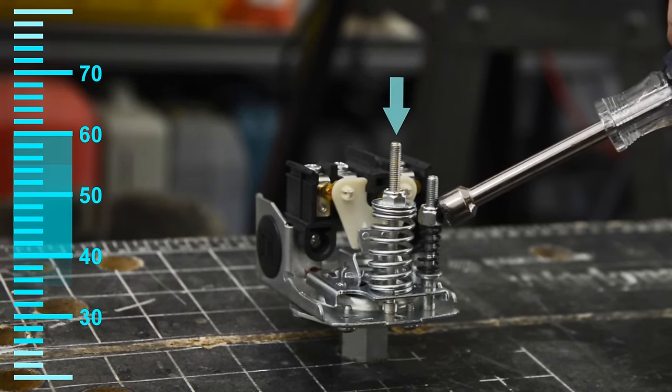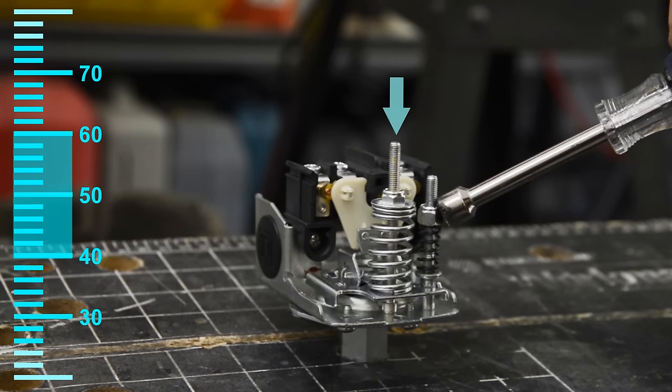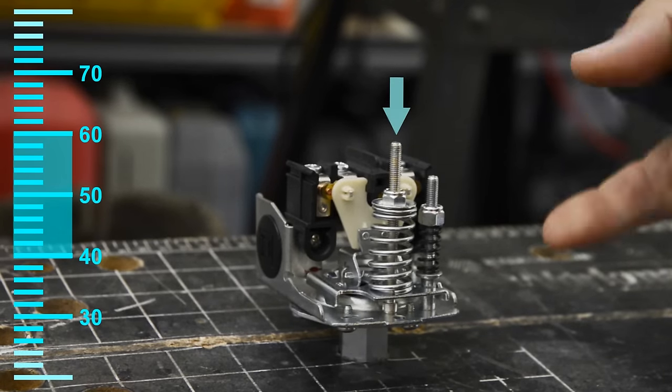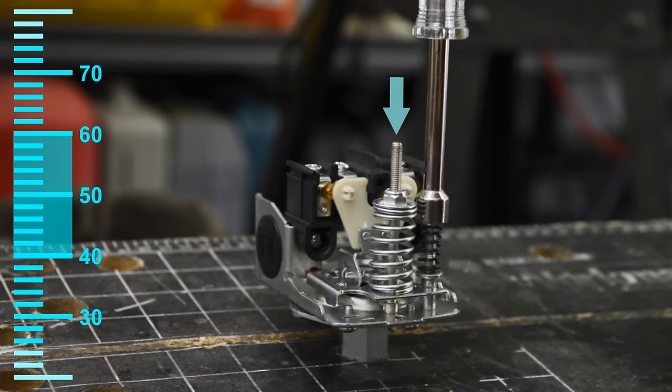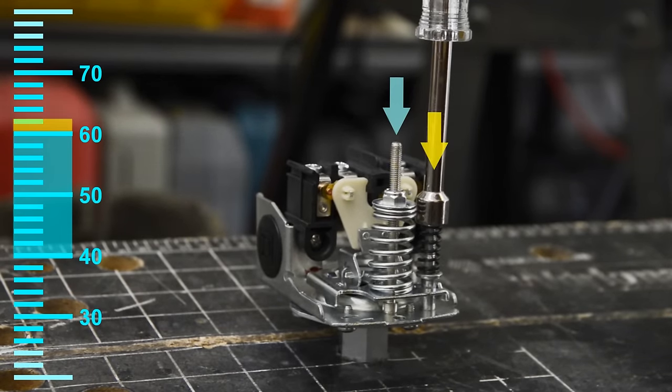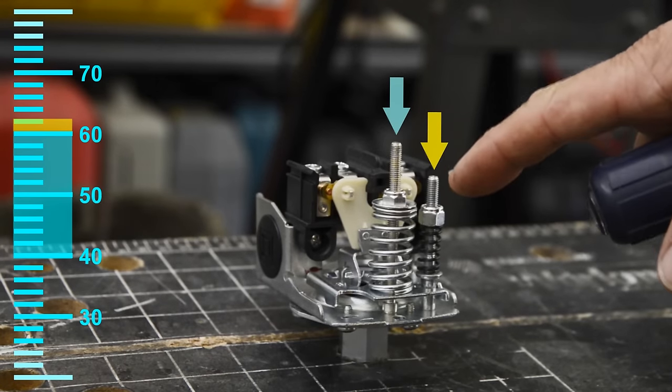The outside adjustment is cut-off only. So if you wanted the range to be 40-62, you could tighten the outside nut, and that would adjust the cut-off only.